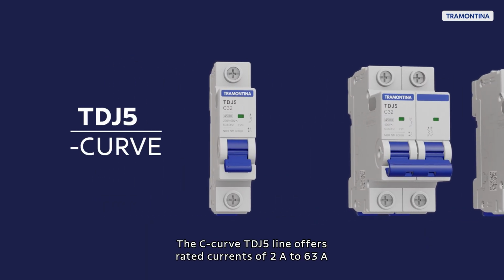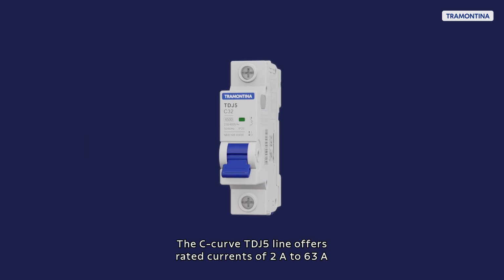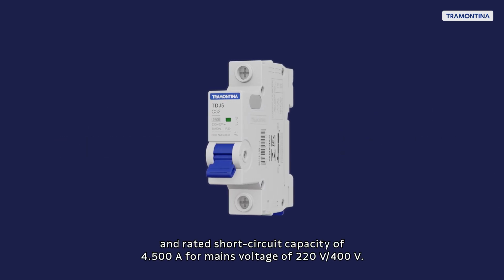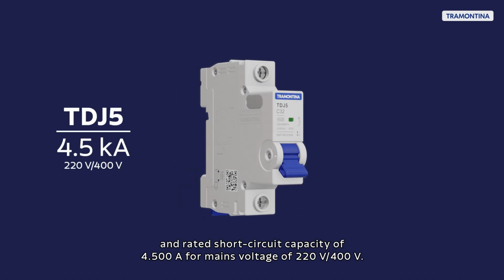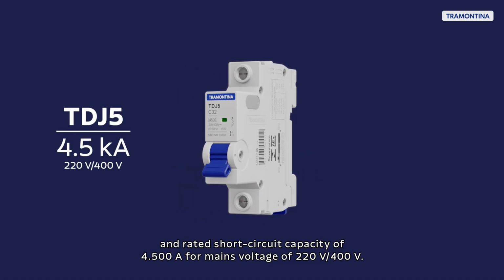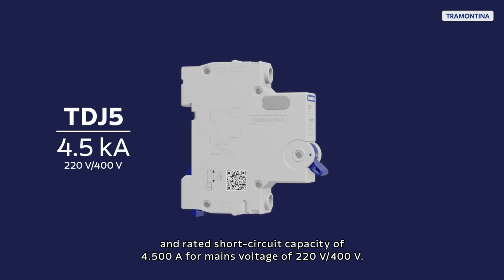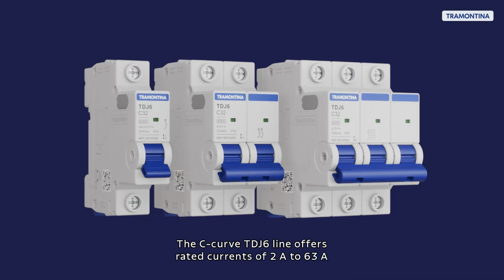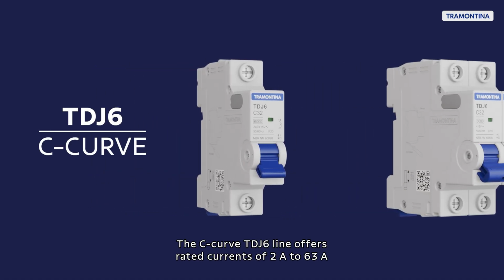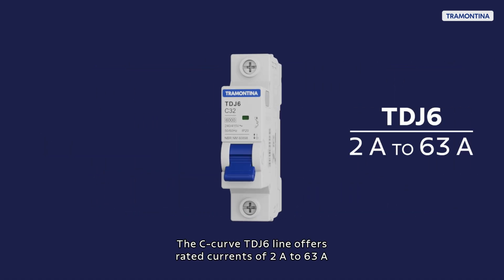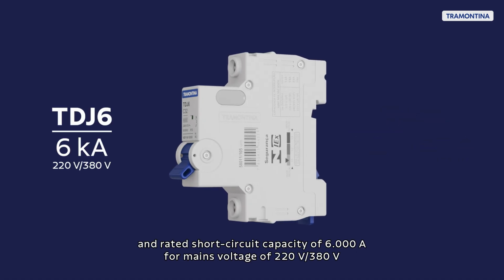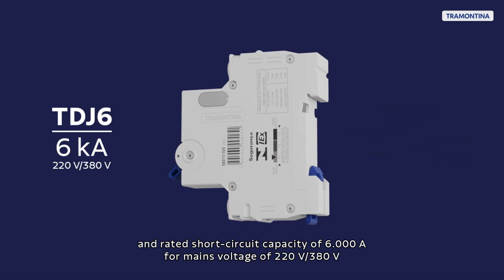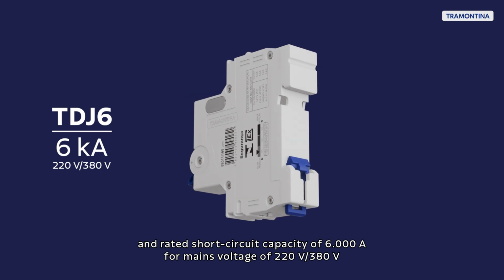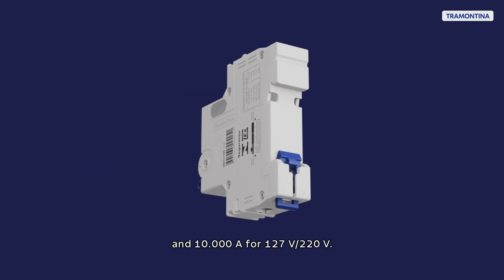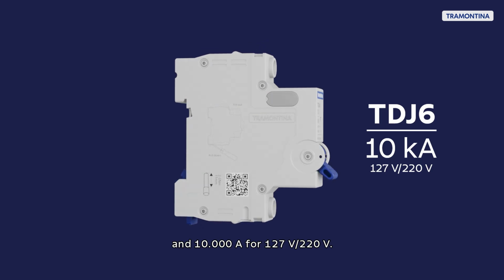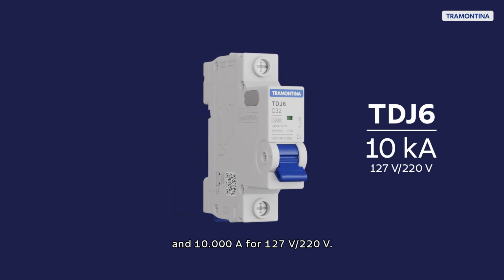The C-curve TDJ5 line offers rated currents of 2 to 63 amps and rated short circuit capacity of 4500 amps for mains voltage of 220/400 volts. The C-curve TDJ6 line offers rated currents of 2 to 63 amps and rated short circuit capacity of 6000 amps for mains voltage of 220/380 volts and 10,000 amps for 127/220 volts.